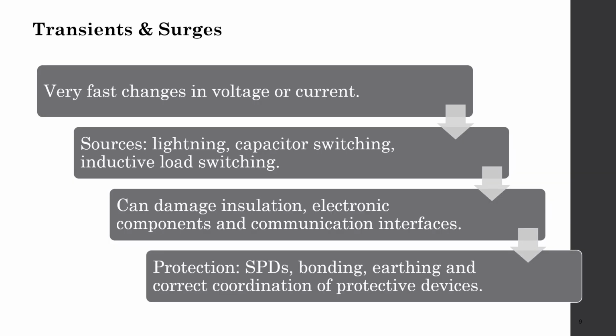Transient and surges. A very fast change in voltage or current is a transient. The main sources of this are lightning, capacitor switching, and inductive load switching. This can damage insulation, electronic components, and communication interfaces. For transient and surges, we use surge protection, bonding, and correct coordination of protective devices for the protection.